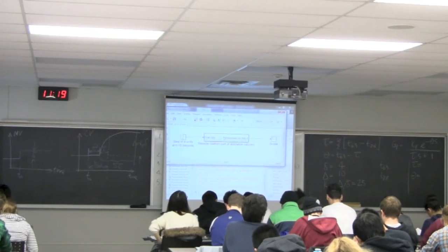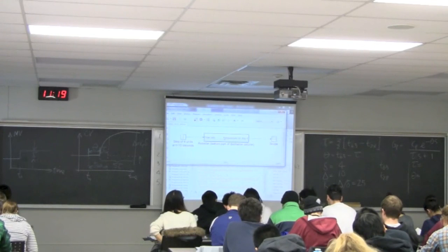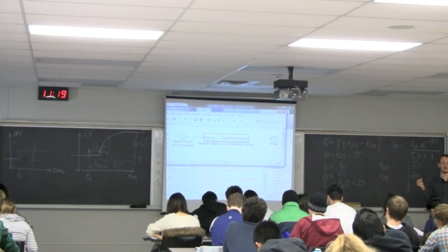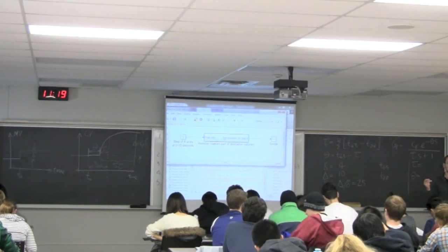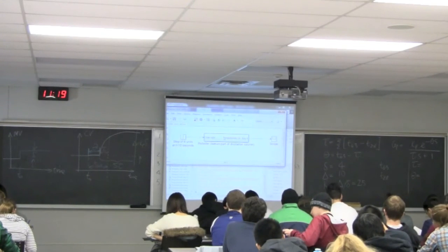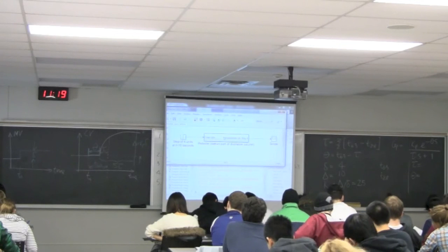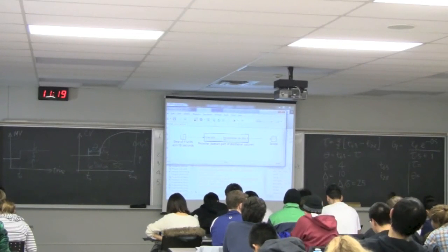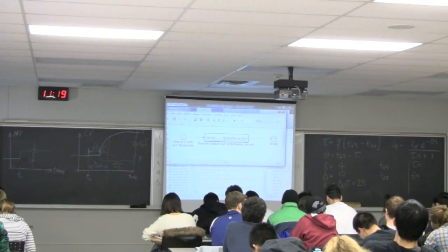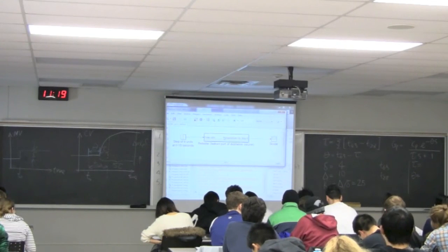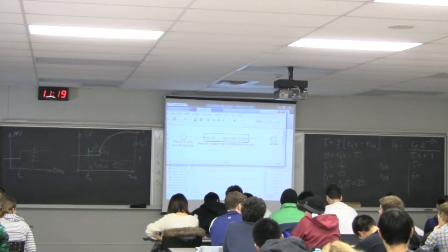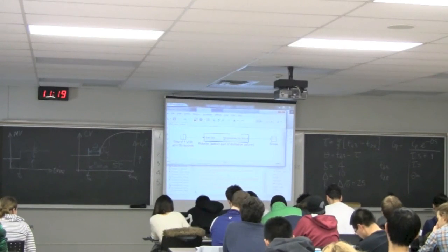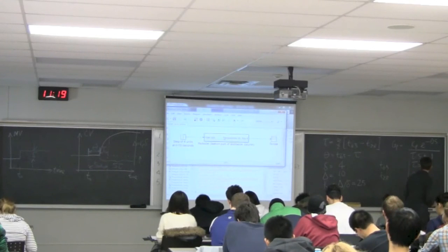If there's error in your KP, theta, and tau, remember what are we using these KP, theta, and tau for? To go tune our controller, okay? So then you go and fine tune your controller to try and find minimum IAE. This is telling you if there's so much noise and error in the system, fine tuning your controller to make IAE really, really small, you're almost just playing around with noise, okay? So just bear that in mind when you're tuning your controllers. Let's take a look though and finish this up.